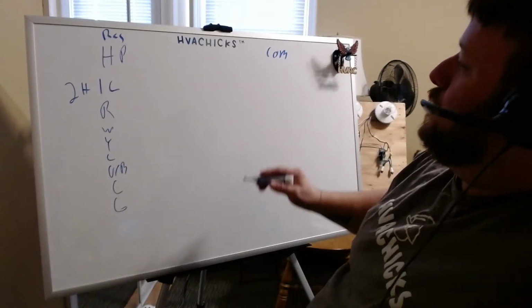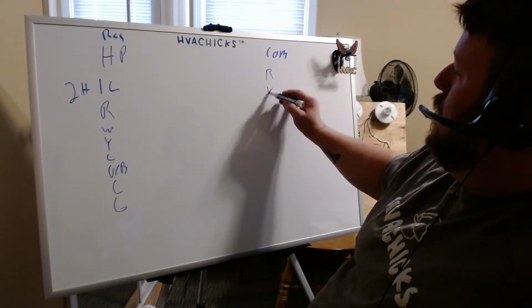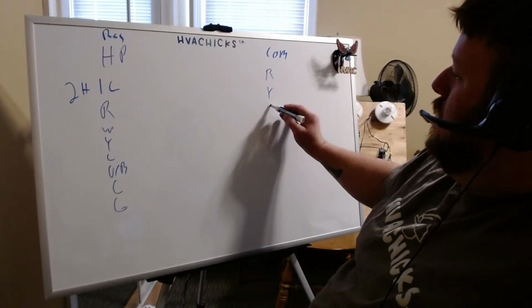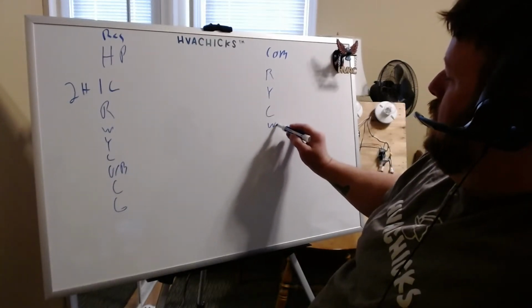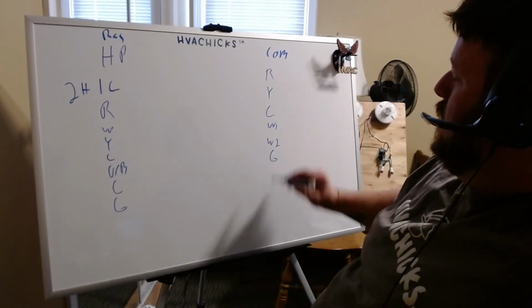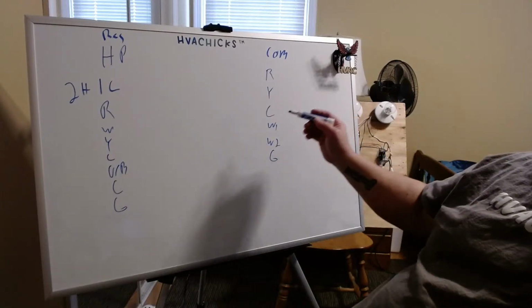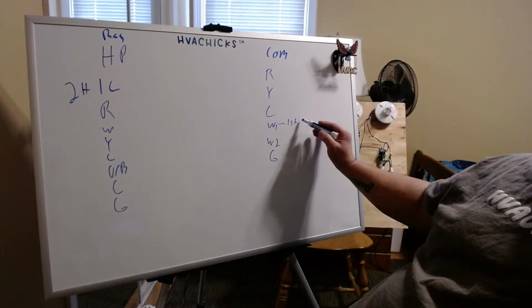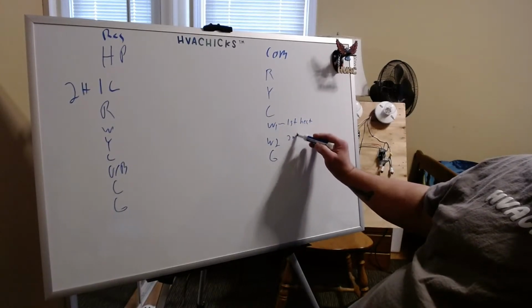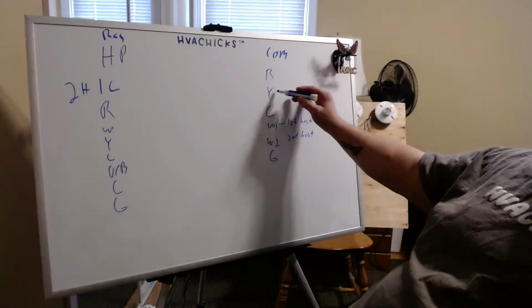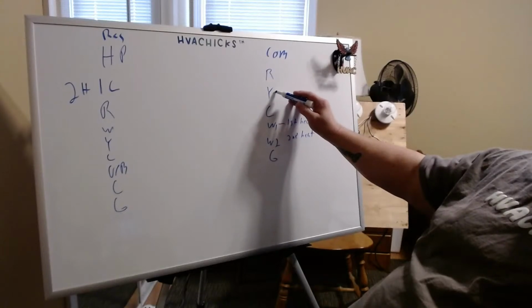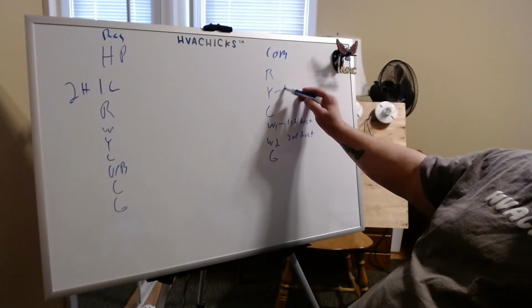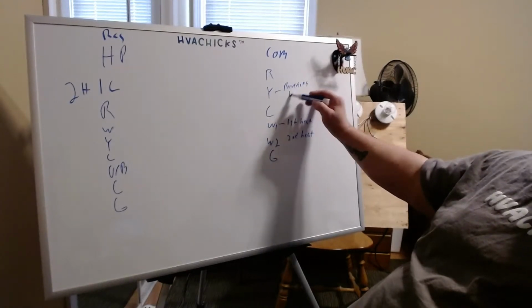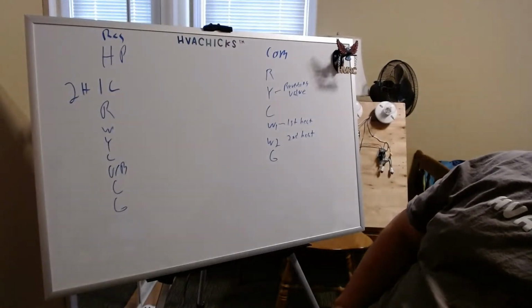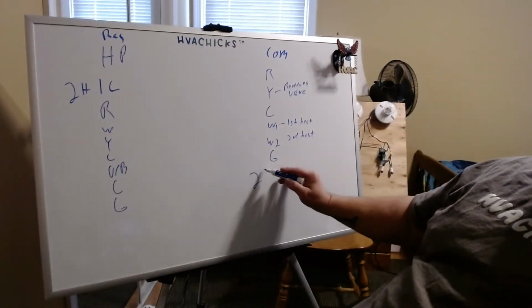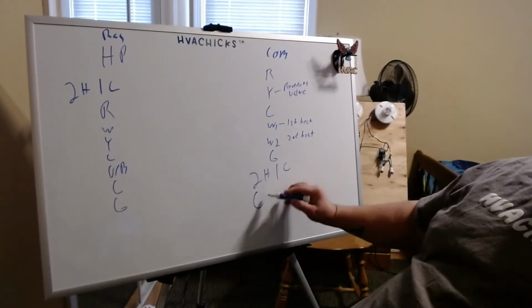but a commercial one: R, Y, C, W1, W2, G. Now we're still going with 2 heat, 1 cool. So when you call for cooling, you're going to energize the Y. Y will also energize your reversing valve. You wire this up as a 2 heat, 1 cool conventional.